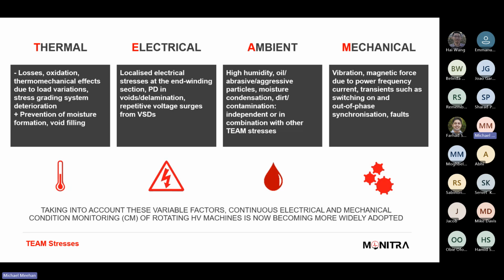High temperature vaporizes moisture, reducing the risk of electrical tracking failures. So that's one advantage of keeping the temperature right as well. When the machine's offline, that's why you have the frame heaters, not sump heaters, just to keep that moisture out of the winding, especially when the machine's in, let's say, a coastal or offshore environment. In general, you don't want the winding to become damp and then start it up. That can actually be a major problem. So controlling the temperature while the machine is offline is a very key feature of being able to maintain a healthy machine.